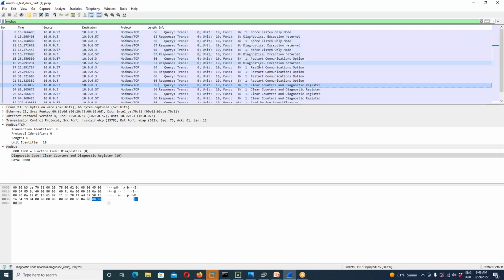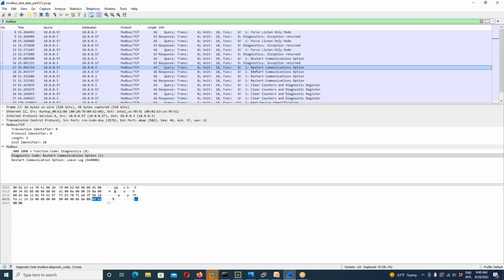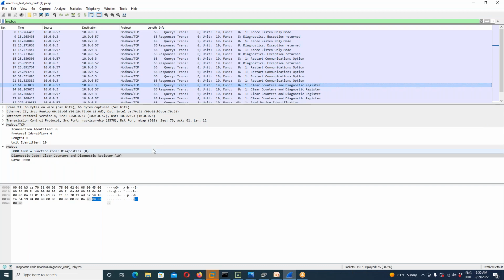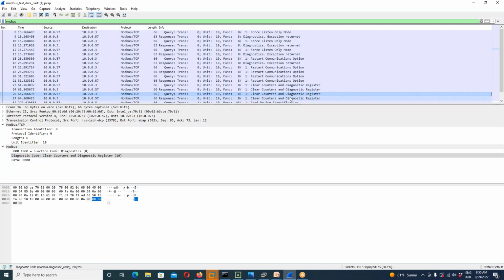So they've forced listen only mode, then started communication option, restart communication option, which you can see clicked here. It's function code 8, restart communication option 1, that's subcode 1. There's about 4 packets there. Then over here we have function code 8, which clears counters and diagnostic register. So we're clearing all the counters on the PLC and the diagnostic register, and you see multiple packets going here for that purpose.